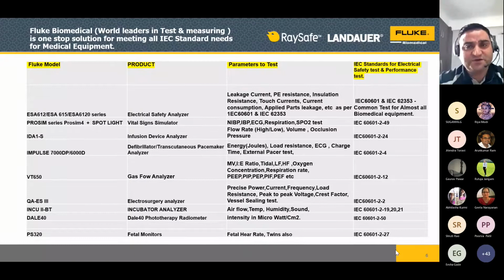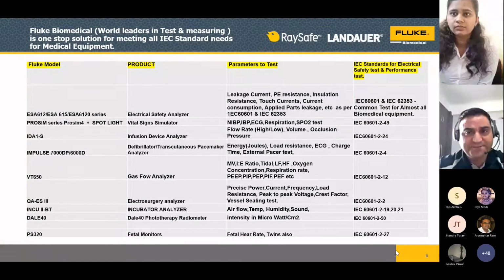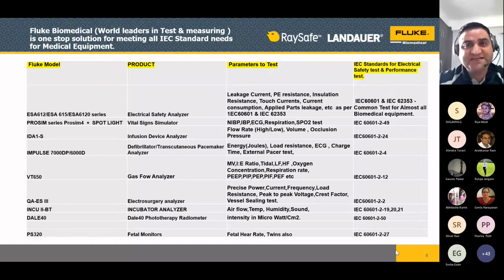And please remember this, IEC 60601 is common for all the medical devices. If you have one electrical safety analyzer, you can do tests for all the medical equipment which are single phase equipment. So what are you going to measure? Leakage currents, protective earth resistance, insulation resistance, touch currents. You can see the current consumption, applied part leakage. We will come to that next.